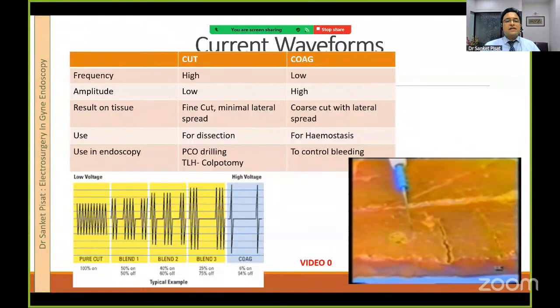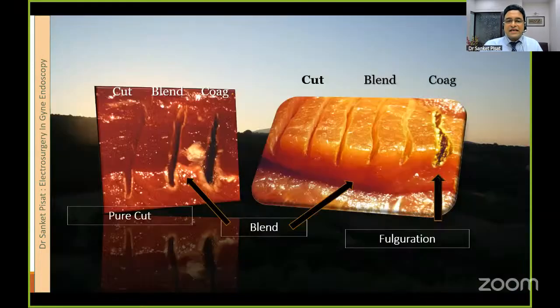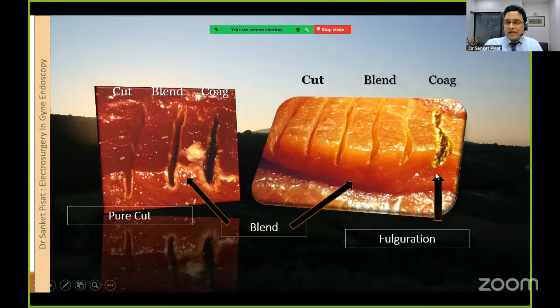So essentially, the cutting waveform is used for dissection, and the coag waveform is used for hemostasis. In endoscopy, the cutting waveform would typically be used for situations like PCO drilling or colpotomy in laparoscopic hysterectomy, and the coag waveform would be used for controlling bleeding or hemostasis. This is again how it looks. You can see here the cut is a smooth cut and the coag is a very ragged and destroyed kind of tissue, denoting how much lateral spread occurs if you change the type of waveform used.